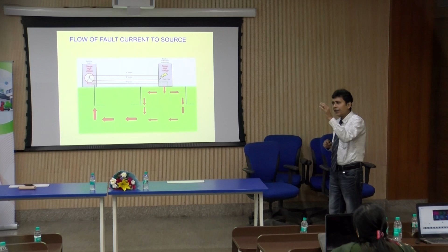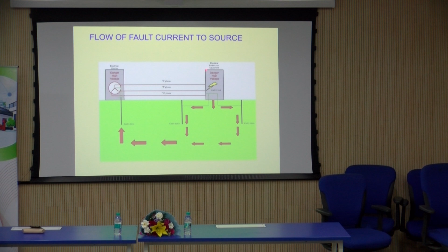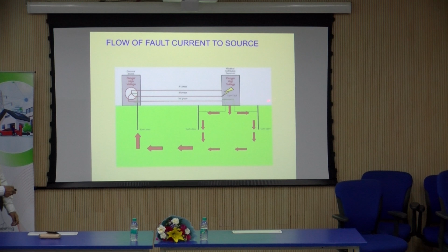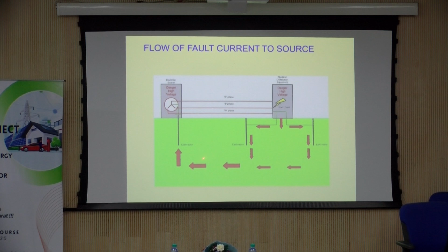To understand that thing, you can refer to this figure to see why grounding is important. In the absence of a dedicated path for that fault current to go back to the source - suppose this is your source, this is your actual system where the fault happens. When it happens, that is called SLG fault, single line to ground fault. It has one choice, to go back to the source through Mother Earth. When it is going back through Mother Earth, let's say the resistivity offered is 10 ohm-meter in a very good condition, it will take time to get back to the source.